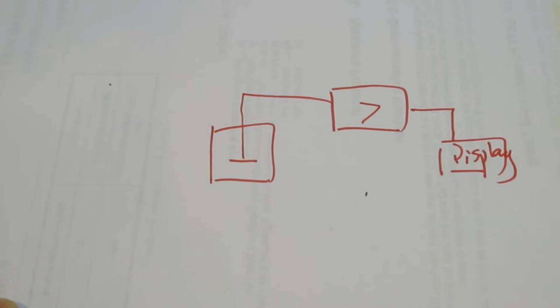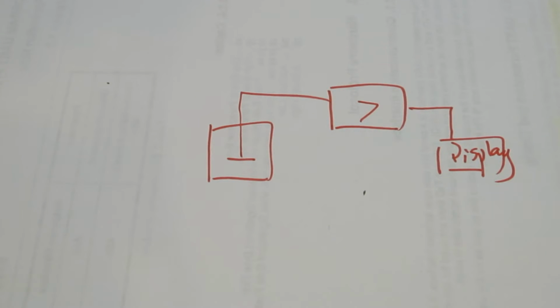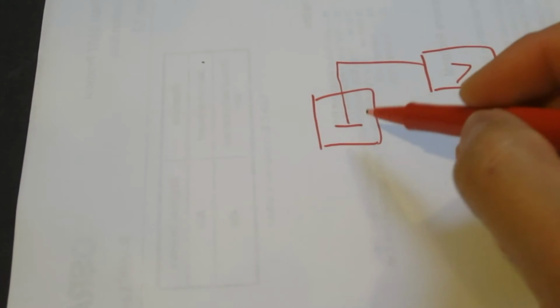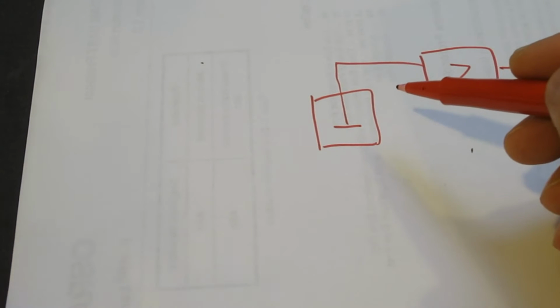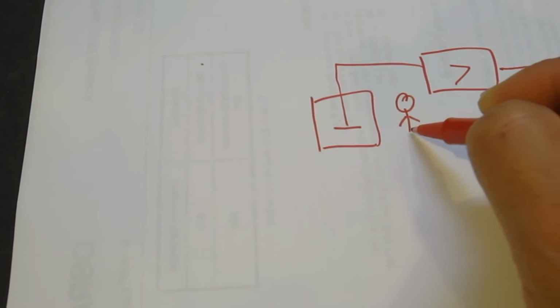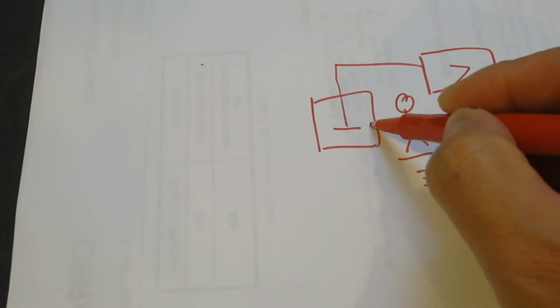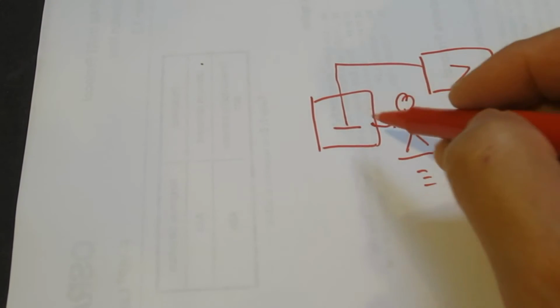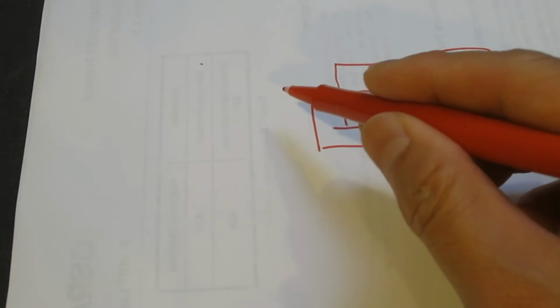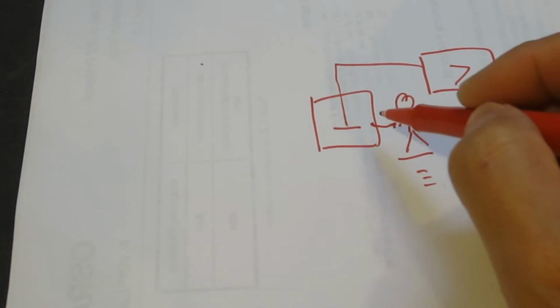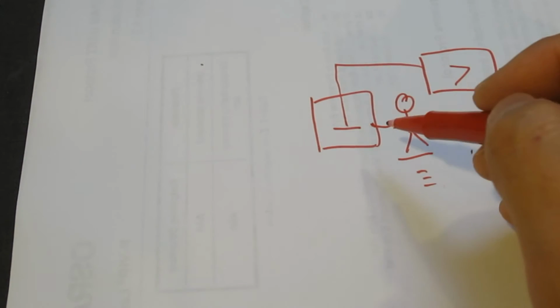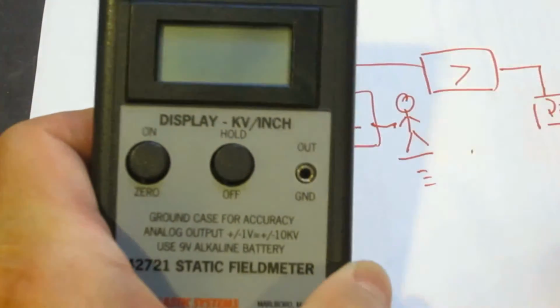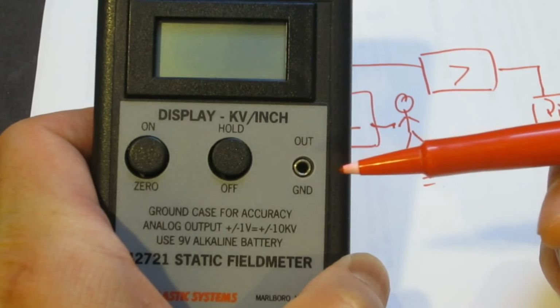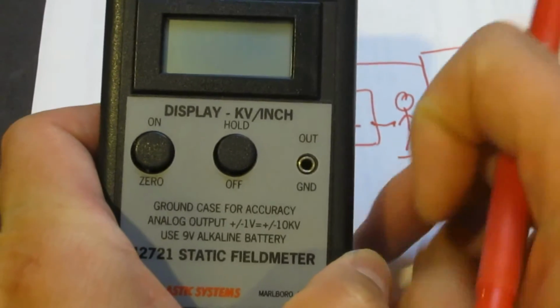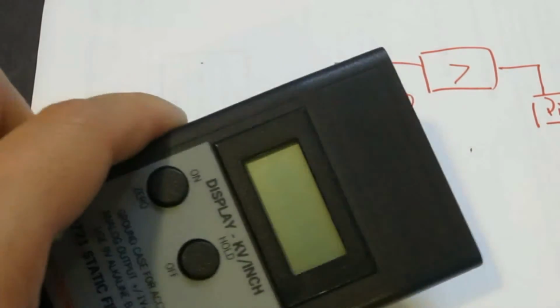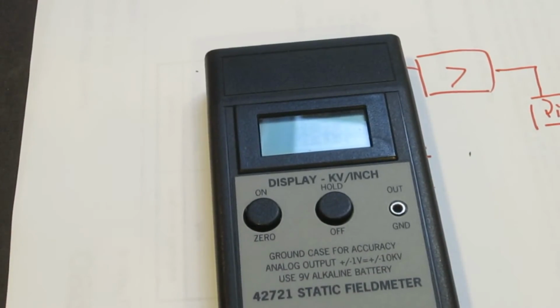Now, by the way, because the sensor has to be ground referenced, typically they assume that the person is ground referenced. So when we are holding this case, and the case is conductive, be it the actual instrument case or the actual sensor case, they're connected, and this should be conductive. That's how they ensure grounding. Alternatively, you can use this plug here to plug in a known ground reference. For that, the case of this instrument has to be conductive. So let's verify that.